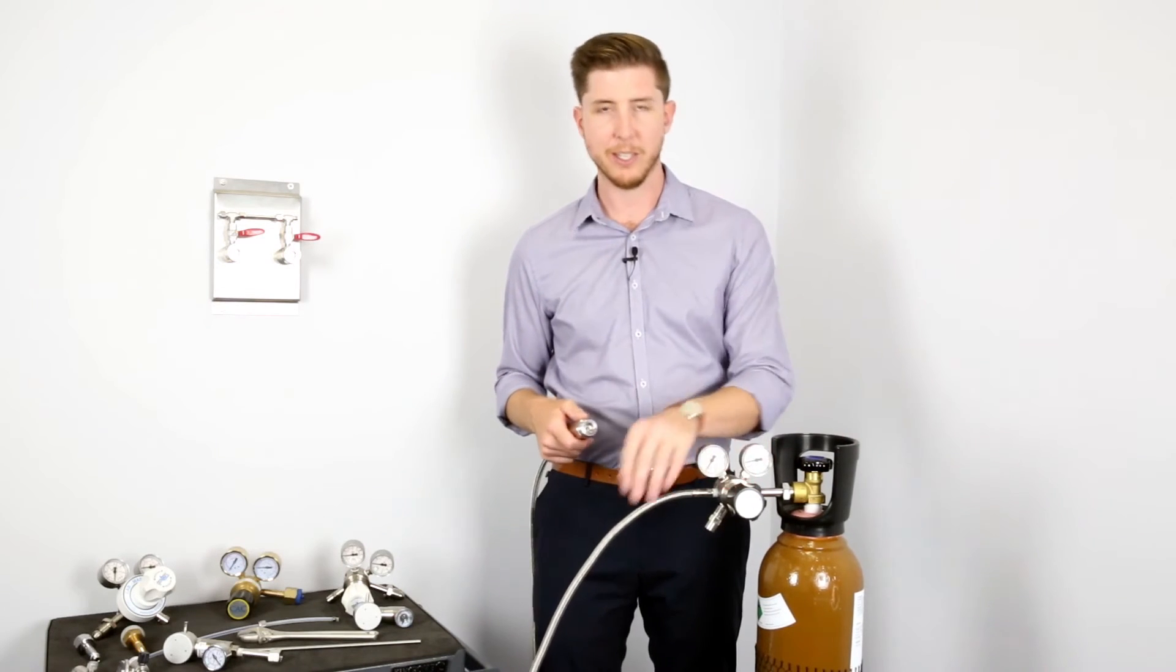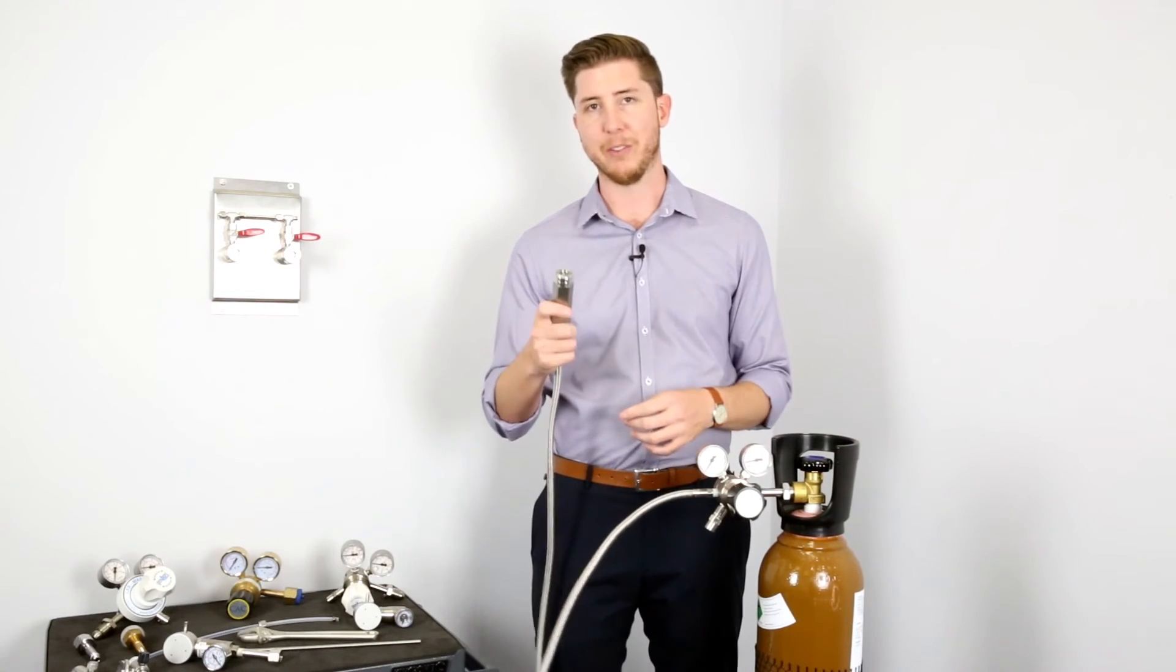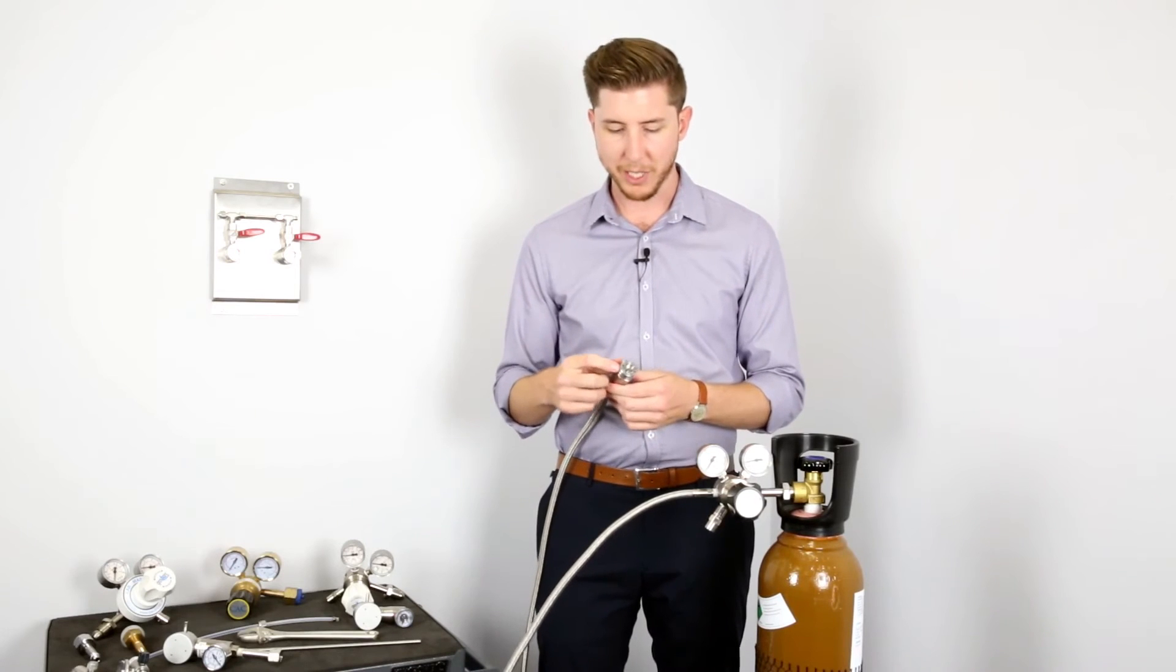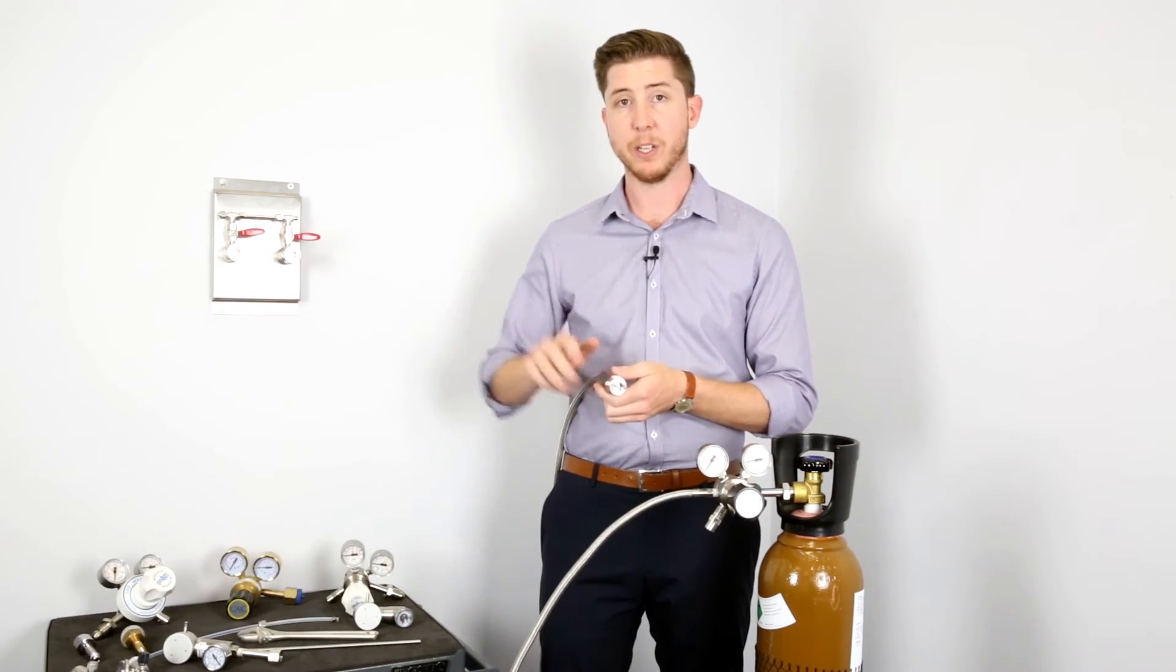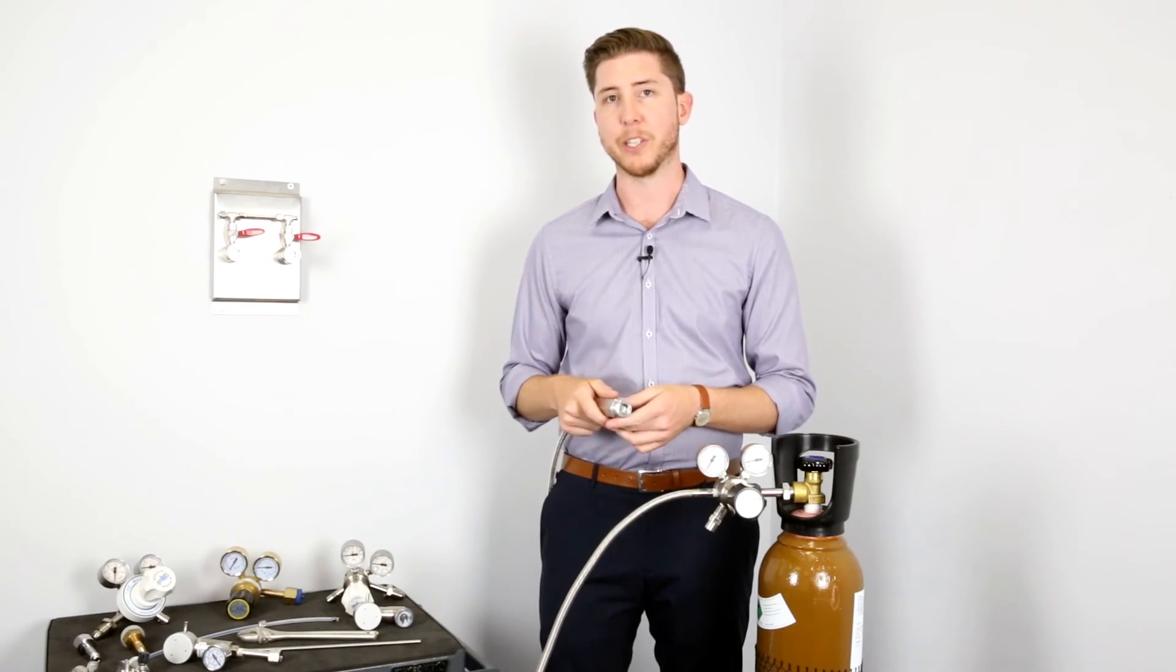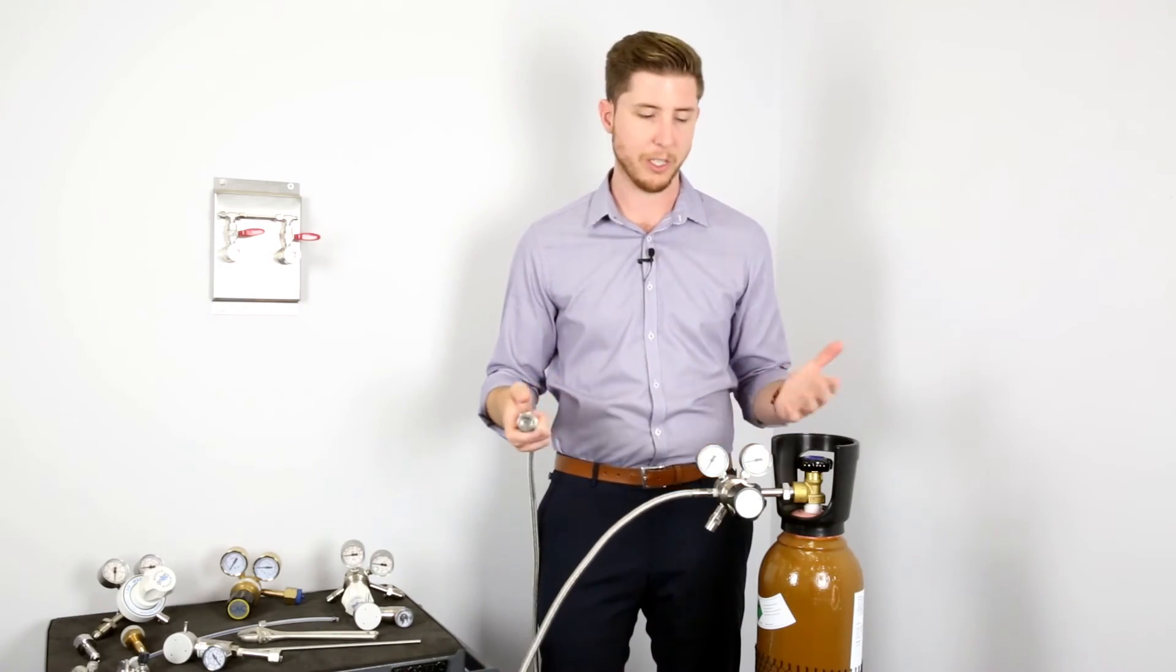If your docking station however requires pressure you'll need a gas cylinder, a pressure regulator, some stainless steel tubing and a valve assembly kit. The valve assembly kit has a C10 outlet mimicking the same valve that's on your disposable cylinder that you're currently screwing into your docking station. Simply screw that into your docking station and you're away.